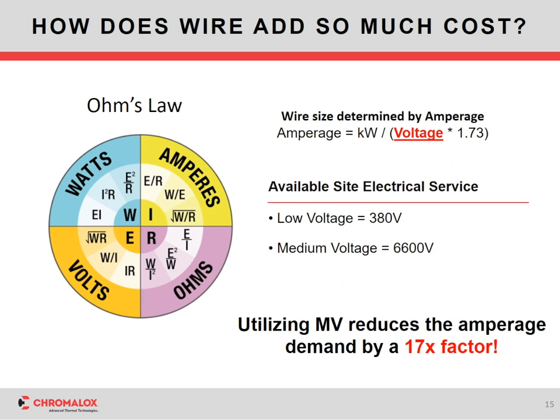So now the difference is when we compare a low voltage system with a medium voltage system. Again, the kilowatts or the heating load is going to stay the same, but if we're able to increase the voltage supply to such a heating system, essentially the amperage comes down by a factor of almost 17 times. Again, we're comparing a system that would traditionally run at 380 volts, that now can be run at a 6600 volt power supply.